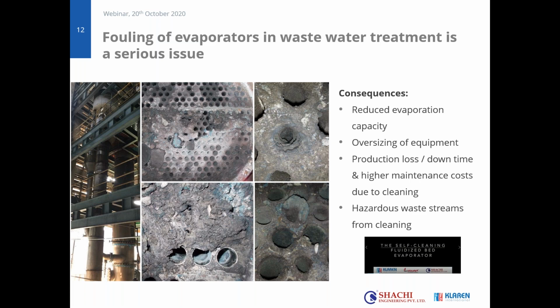And you see some real nasty pictures of a fouling case on the left side. Of course, if you have these types of fouling in your heat exchanger, this will affect the performance. And as I already said, it will lead to reduced capacity. But already in the design, it will also lead to oversizing, because in the design you need to take into account the fouling layer and the effect on heat transfer. So that will result in additional heat transfer area.